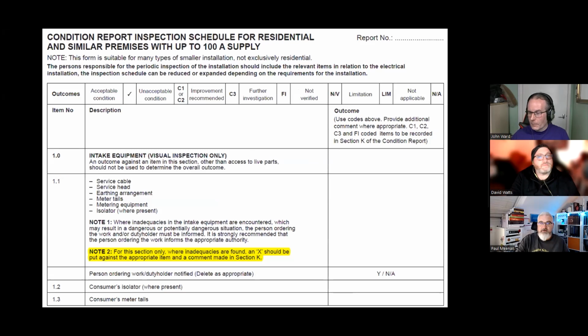Moving on, EICR form, pretty much no real change there. However, on the condition report for domestic, in the schedule of items inspected, so this is the bit behind the schedule of items inspected, there is under intake equipment the requirement still to inspect the service cable, service head, earthing arrangement, meter tails, metering equipment, and isolator. There is a note 1 that says, where inadequacies in intake are encountered, which may result in a dangerous or potentially dangerous situation, the person ordering the work and/or duty holder must be informed. It is strongly recommended the person ordering the work informs the appropriate authority. Note 2, for this section only, where inadequacies are found, an X shall be put against the appropriate item and a comment made in section K.